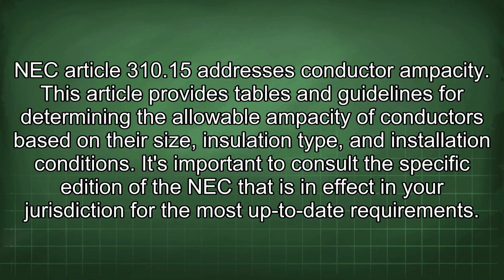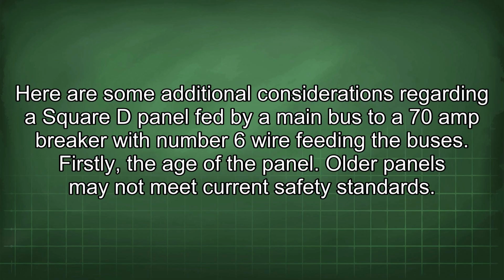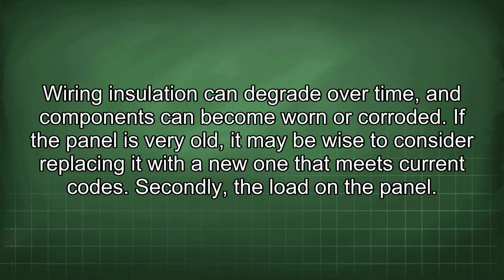the most up-to-date requirements. Here are some additional considerations regarding a Square D panel fed by a main bus to a 70 amp breaker with number 6 wire feeding the buses. Firstly, the age of the panel. Older panels may not meet current safety standards. Wiring insulation can degrade over time, and components can become worn or corroded. If the panel is very old, it may be wise to consider replacing it with a new one that meets current codes. Secondly, the load on the panel.